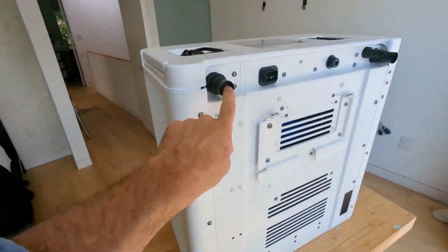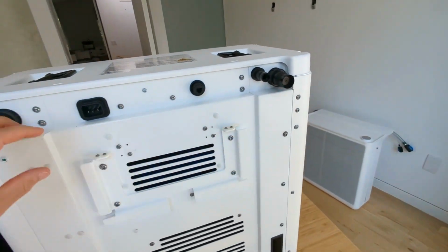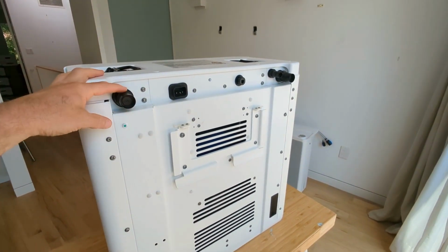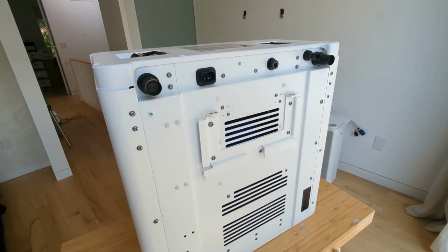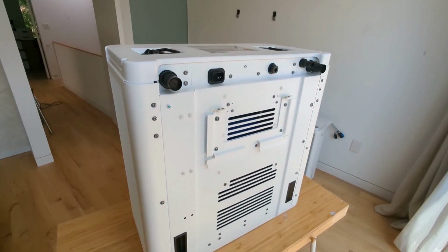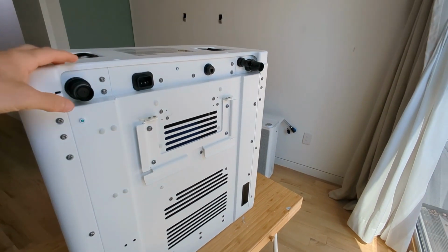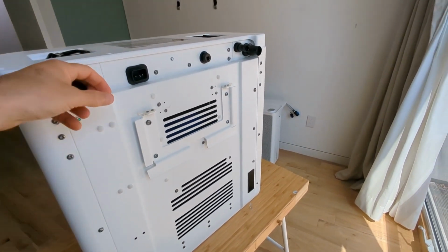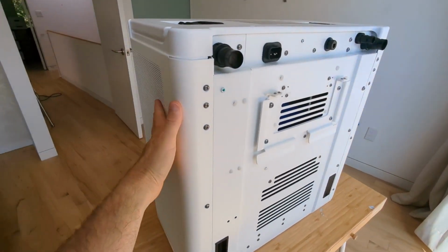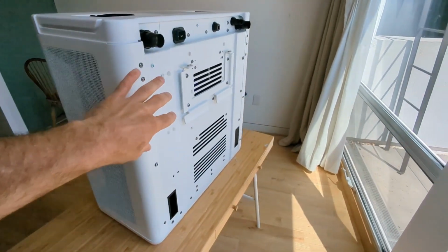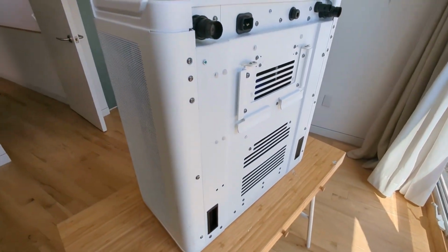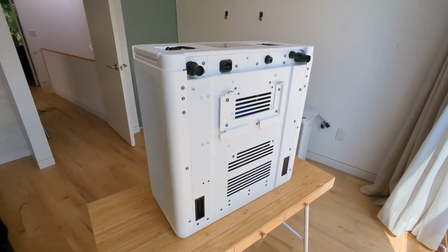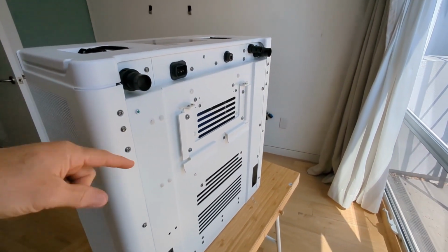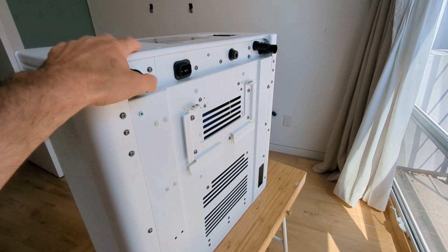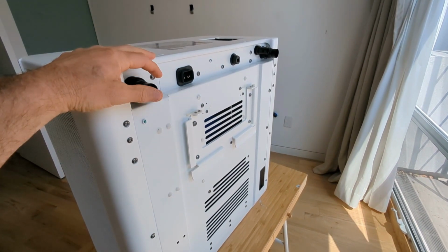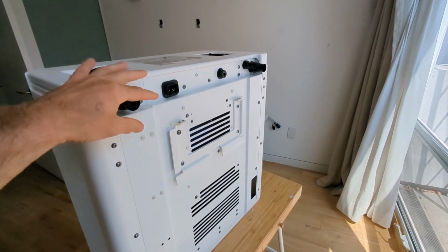The first thing you'll notice is these ports here, which tells us that this unit is circulating coolant between the indoor and outdoor unit rather than refrigerant, which was an interesting choice. It means that everything's simpler because you don't have to have the refrigerant going out of this unit. It's completely sealed in here, but you do have to have a heat exchanger in here, which you lose some efficiency, both because there is a delta T across that heat exchanger and also because you can't move as many BTU through liquid as you can through a refrigerant that goes through a phase change as it goes around the loop.